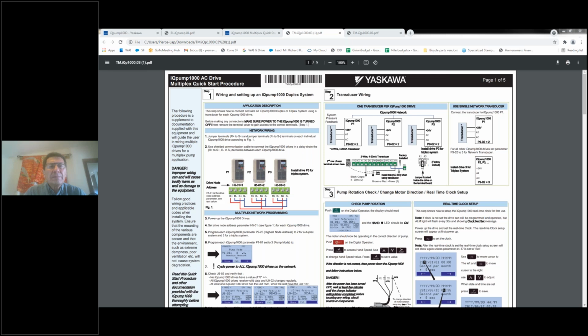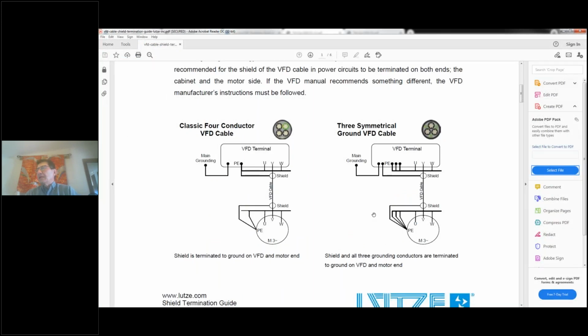Now, the other thing about inverter duty cable is that it reduces wear and tear on the motor insulation. And it also allows a, here, let me just put this up here. Good grief. I'm definitely having some significant navigation issues on my computer today. So this is the symmetrical ground VFD cable with the three small grounds as opposed to one big ground. What's the advantage of this? You get geometric symmetry between the conductors and better noise cancellation.